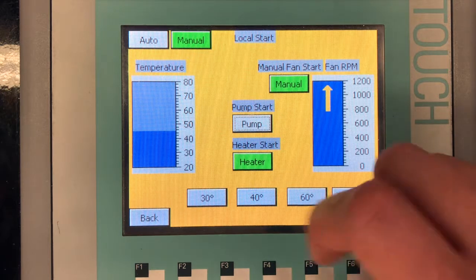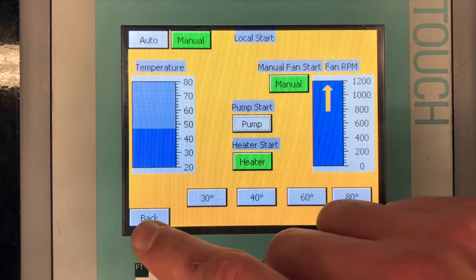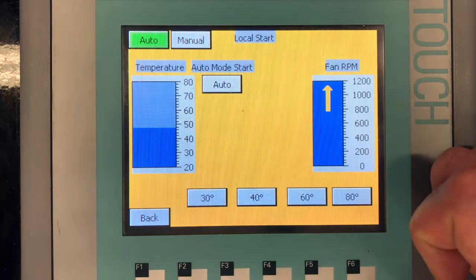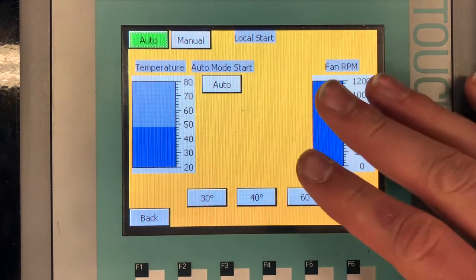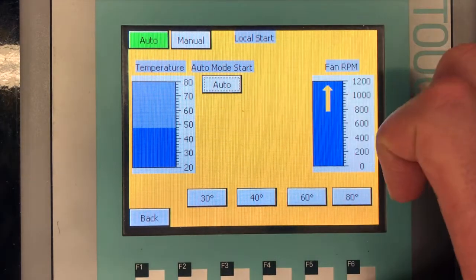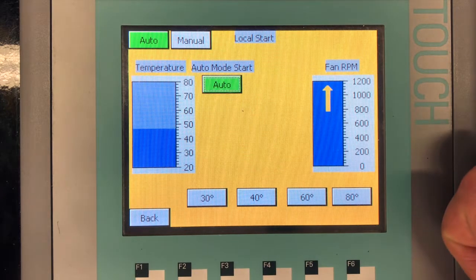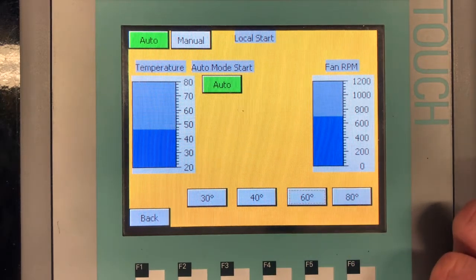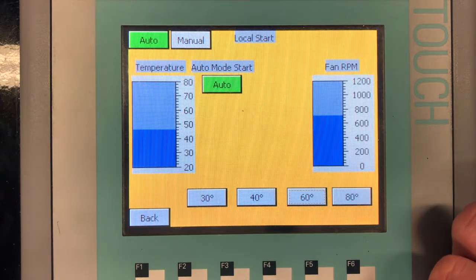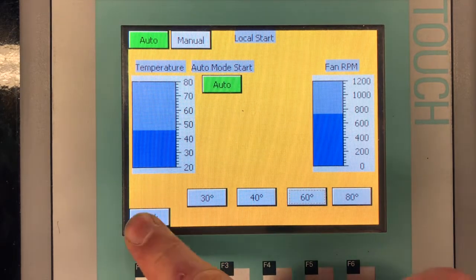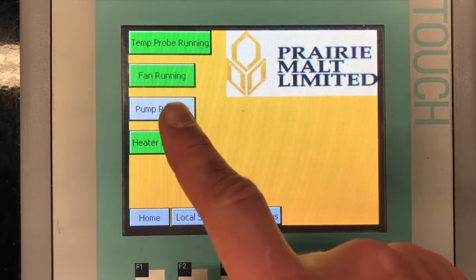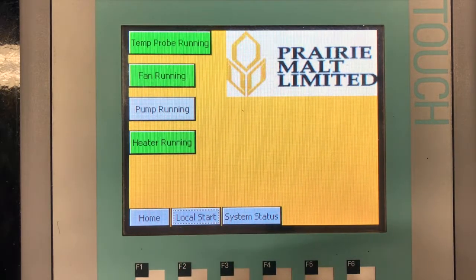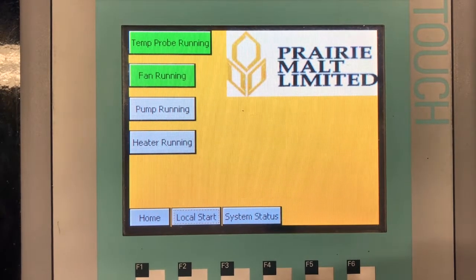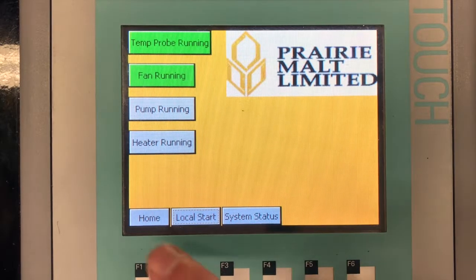So as you can see, we were still in manual mode, and right now we just transitioned over to auto mode. He put it on auto mode start, and he selected a 60 degree preset temperature. Right now, back on the main screen, we can see the fan's running, the heater's running, and the temperature probe's running, and the heater was just disengaged. So clearly that's a sign that it's hit 60 degrees.